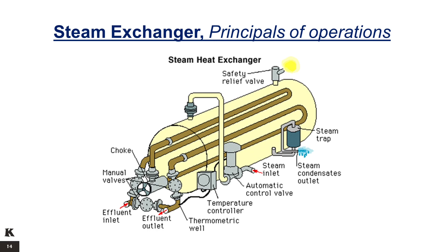Steam heat exchangers are required in certain geographical locations where regulations do not permit the use of direct fired heaters. As there are no naked flames, the steam exchanger is intrinsically safe in terms of risk due to fire. Whenever the steam heat exchanger is anticipated, it is necessary to check the availability and characteristics of the steam supply. Most offshore rigs do not have sufficient steam generation capacity. Under these circumstances, it is required to supply a steam generator, which is usually rented from a specialist firm and located in a safe area on the rig.